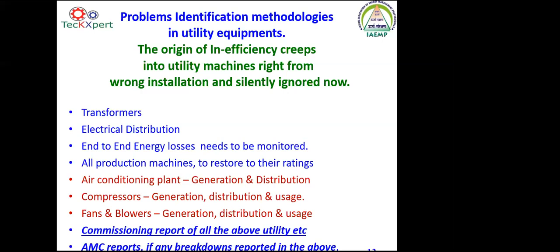So the end-to-end losses, especially the energy losses in all the utilities, from the transformer to the HT/LT loss, have to be monitored daily, and we ask where we stand. Are we at 0.5%? At 1%? At 1.5 or 2%? Especially the transformer losses have to be studied. It is a daily recording of our industry's parameters: electrical distribution losses, and the end-to-end voltage drops, as I was telling, 420 to 380 or 410, where it is happening. What is the amount of loss? Thanks to IoT devices, you can have alarms which pick this up and prompt you. It can give you the input.